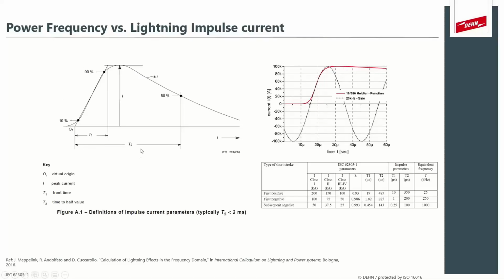Now, this function is also known as the Heidler function, or a double exponential function, as it rises exponentially and decays exponentially. Now, there is a white paper that describes this from the developers of XGSLab with a professor, and they actually did some calculation to show what it would typically look like if we had to characterize an impulse as a sine wave. So they considered the rise time itself, and for a 350 microsecond or first positive lightning stroke, they said the equivalent sine wave would be a 25 kilohertz sine wave. So what we immediately take away from this is that lightning has a very high frequency behavior. Now, first positive strokes only make up about 10% of all lightning strikes across the world.